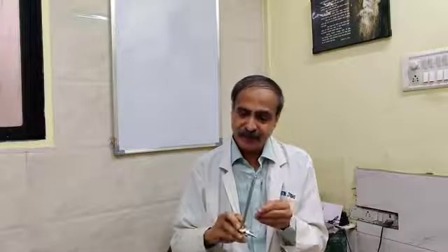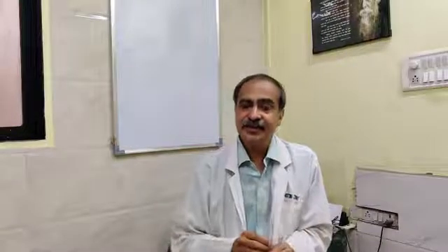So the current, rather than being given to the tissue, is diverted to the instrument. There is a current leakage, and whatever current is leaked is not available for cutting or coagulation, resulting in poor cutting as well as poor coagulating power.